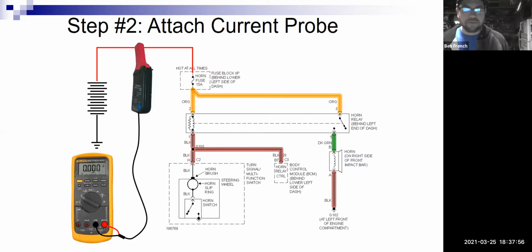Put on the low amps probe, and probably the easiest way to do this is you could take the fuse out and put in a fuse jumper wire, then put your amp clamp around that jumper wire to do the measurement.